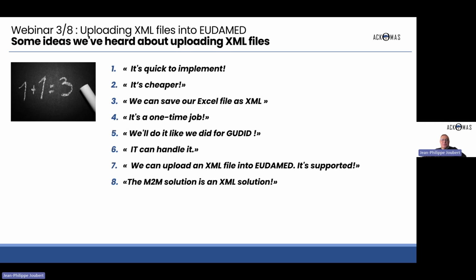And the two next ones: we can upload an XML file into EUDAMED. It's supported. This statement is true. We'll see it in the next part. And the final one, the M2M solution, machine-to-machine solution, is an XML solution. This statement is also true, yet the approach for manufacturers is radically different. But we will see that later on during a coming workshop.